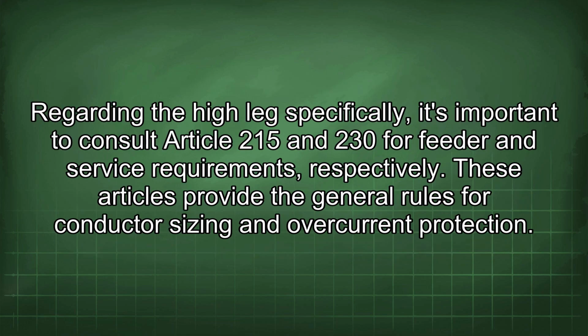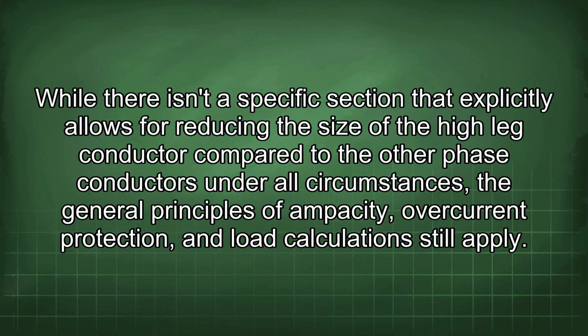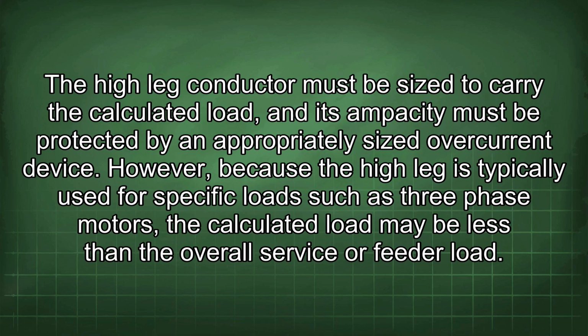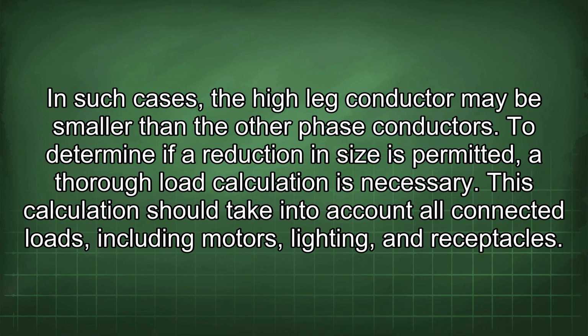conductor size. Regarding the high leg specifically, it's important to consult Article 215 and 230 for feeder and service requirements, respectively. These articles provide the general rules for conductor sizing and overcurrent protection. While there isn't a specific section that explicitly allows for reducing the size of the high leg conductor compared to the other phase conductors under all circumstances, the general principles of ampacity, overcurrent protection, and load calculations still apply. The high leg conductor must be sized to carry the calculated load, and its ampacity must be protected by an appropriately sized overcurrent device. However, because the high leg is typically used for specific loads such as three-phase motors, the calculated load may be less than the overall service or feeder load. In such cases, the high leg conductor may be smaller than the other phase conductors.